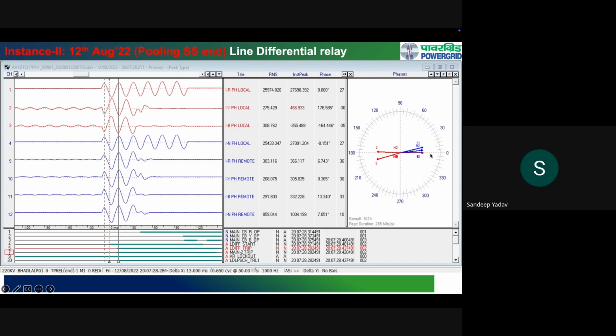So if you take a look at these blue phasors, they're more or less in phase, which is the characteristic of zero sequence currents. So all we see in case of a phase to ground fault is relatively lower fault currents, and they're all in the same phase. So all we see is a zero sequence current contribution from the solar plant side.